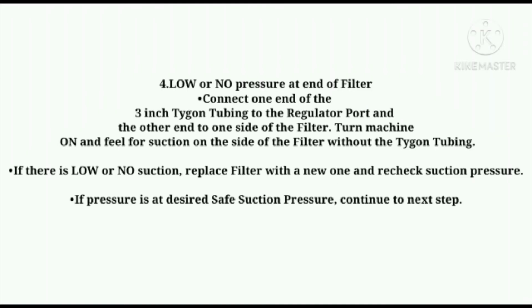The fourth problem, low or no pressure at end of filter. You must connect one end of the 3-inch Tygon tubing to the regulator port and the other end to one side of the filter. Turn machine on and feel for suction on the side of the filter without the Tygon tubing. If there is low or no suction, replace filter with a new one and recheck suction pressure. If pressure is at desired Safe Suction Pressure, continue to next step.